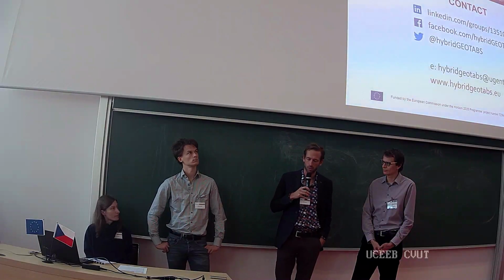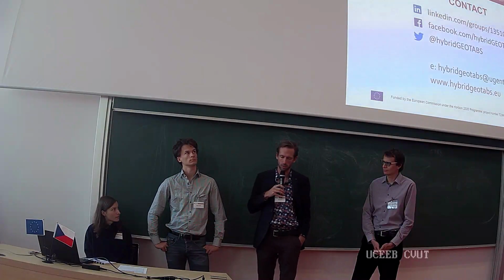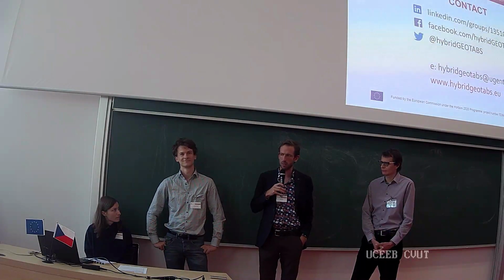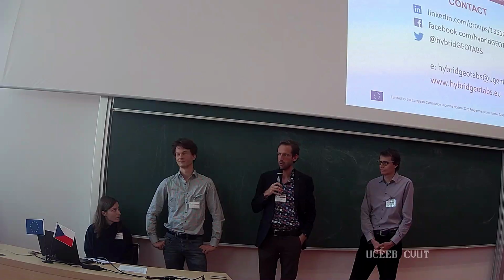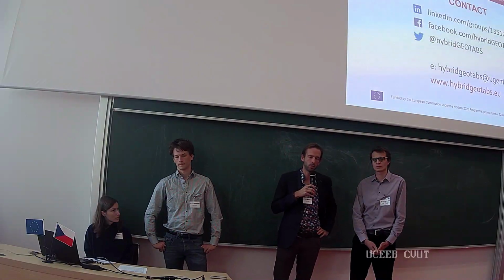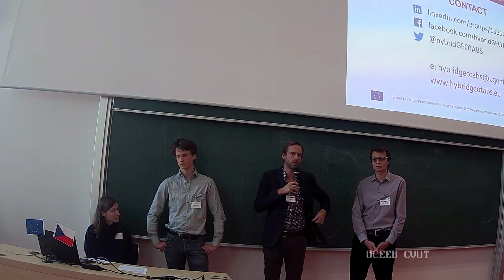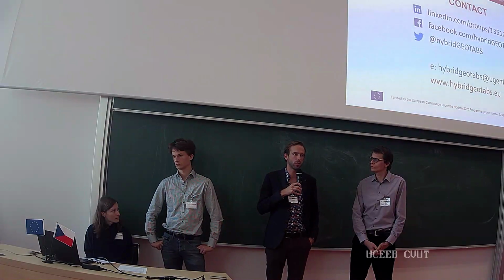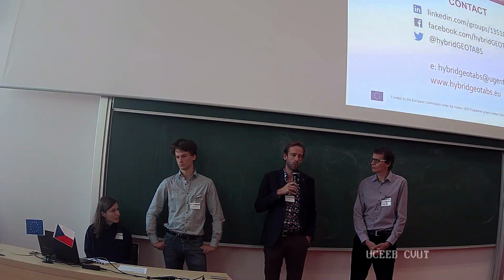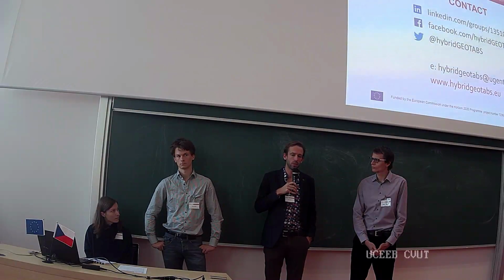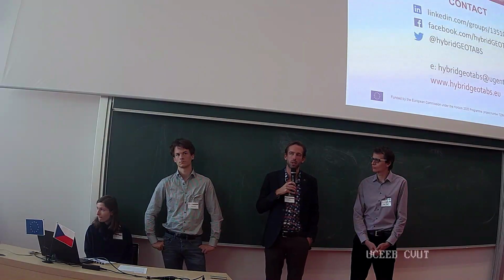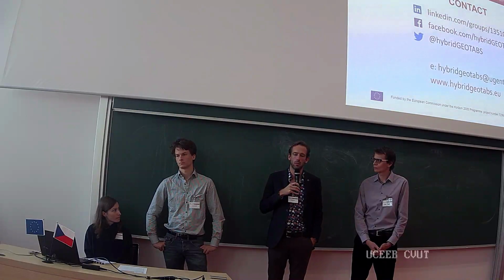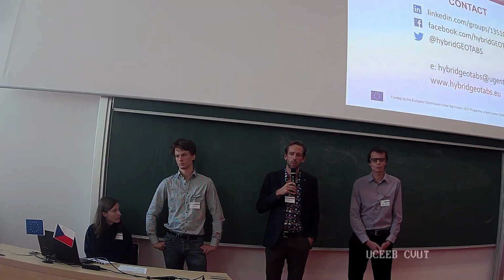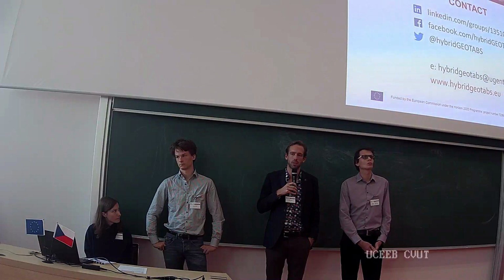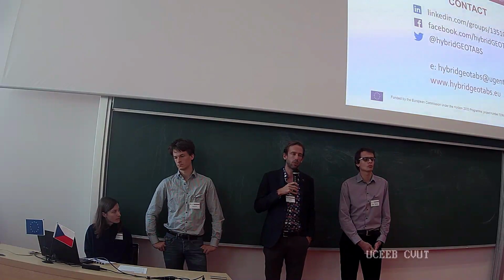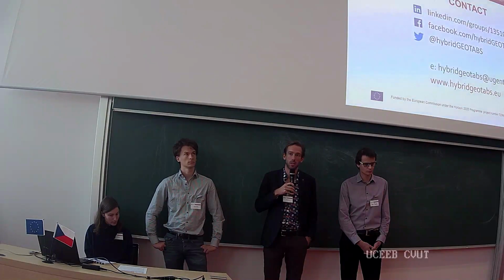Yeah, I think I covered that during the slides, but I'll go over it again quickly. Part of it is the COP that increases from 4.5 to 5.5, which on the heating loads is an efficiency increase of 20%, but in the overall energy budget it's not that much. Where we also gained a lot was on the frequency control of pumps and fans, which had a much larger impact—I think that's where we got savings in the order of 70% on that part of the load, which was in the order of about 30%.